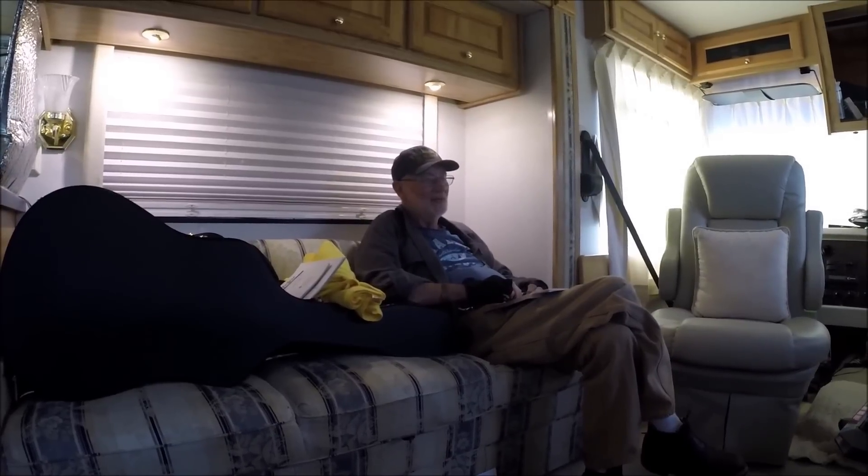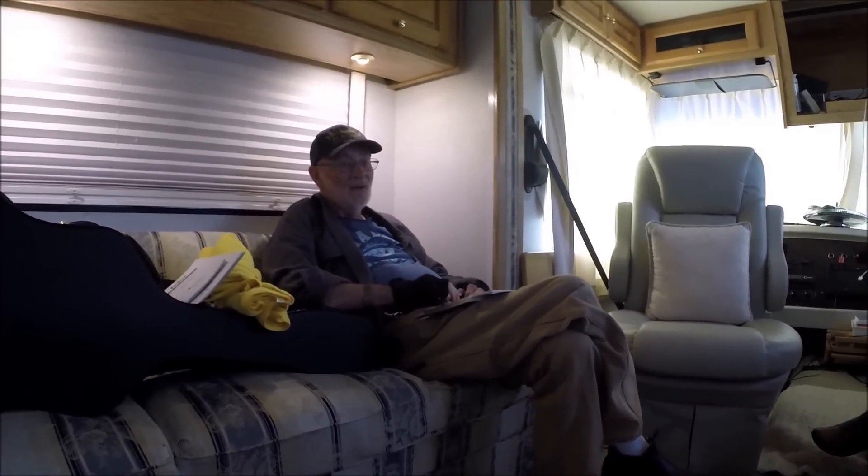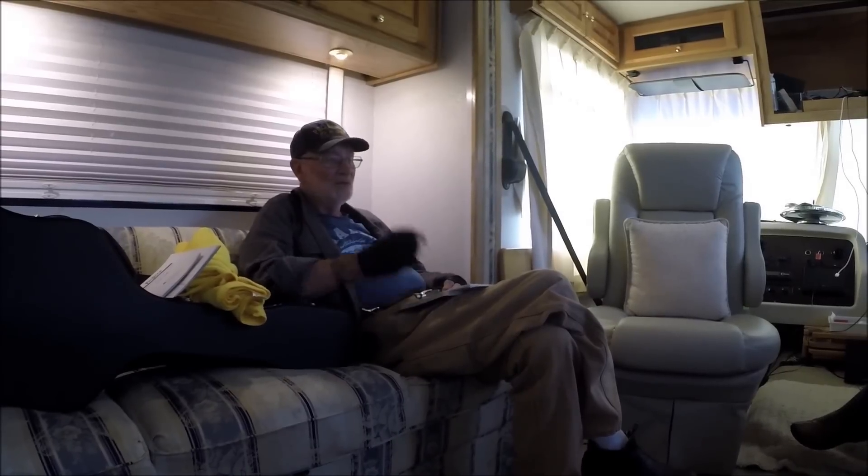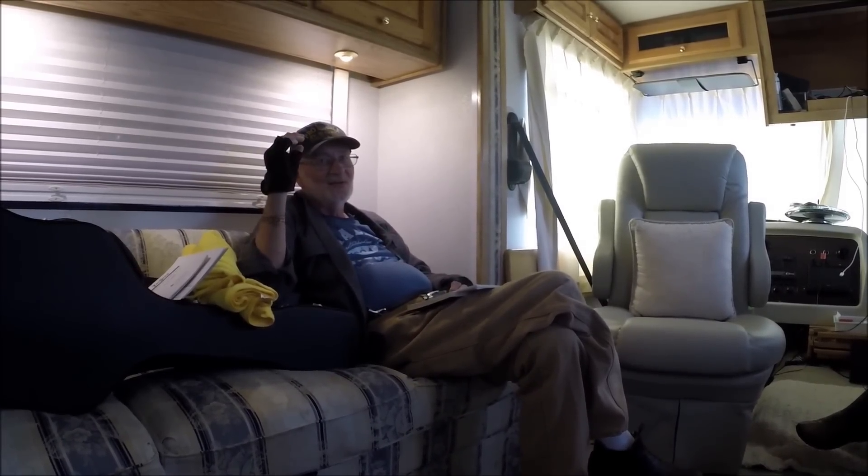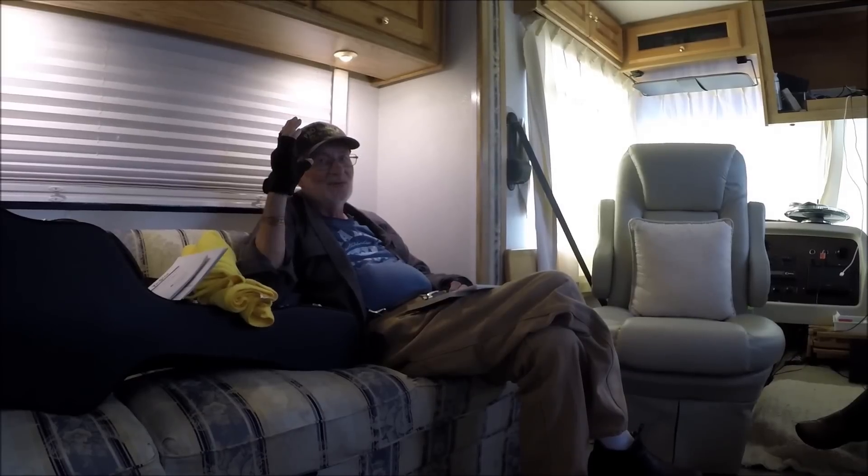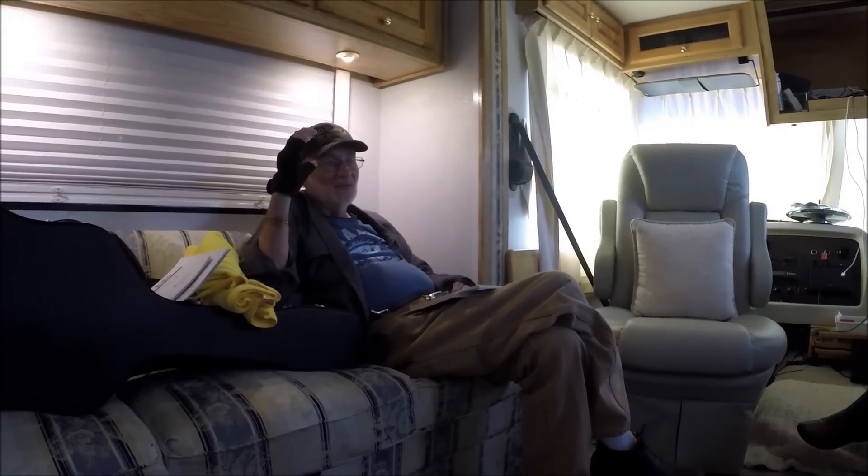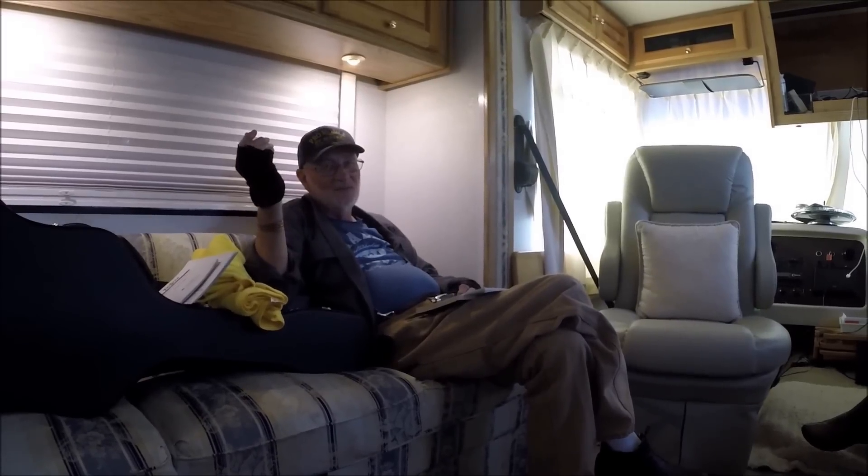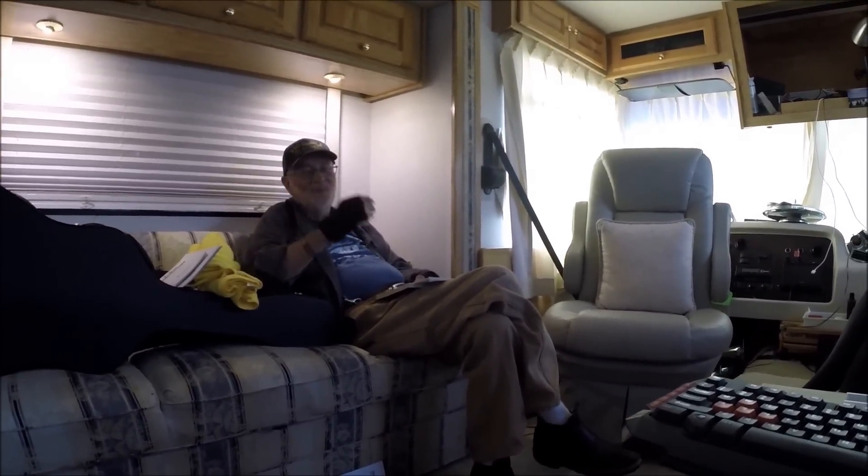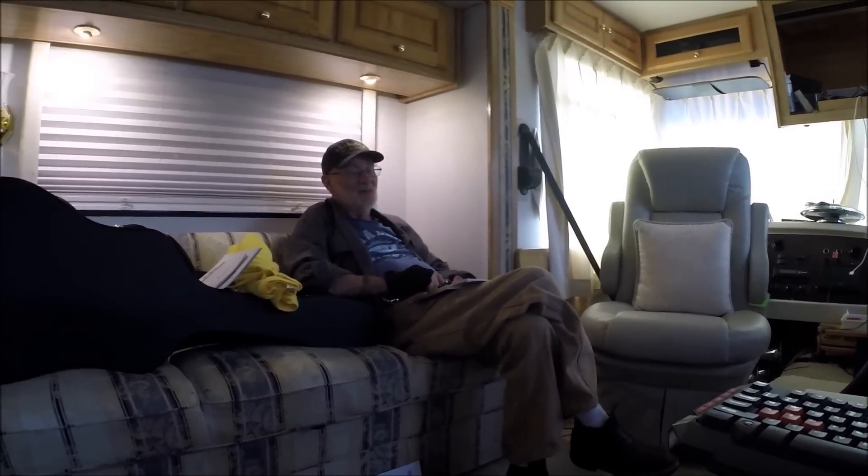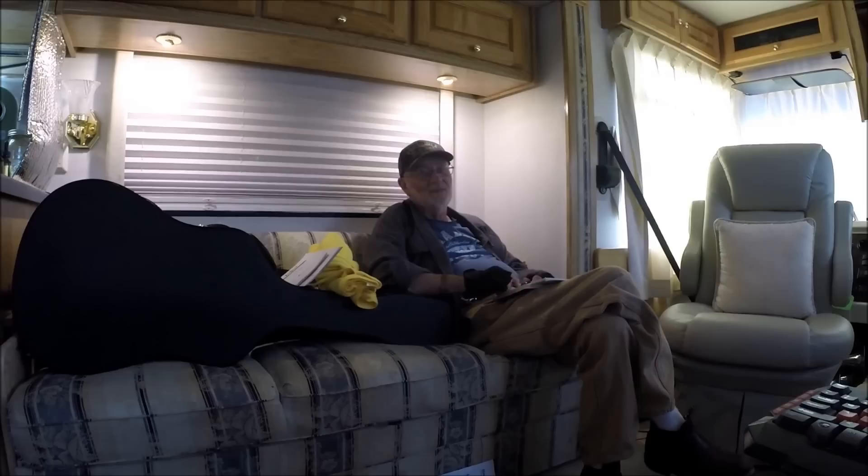We usually put at least a thermal breaker, something like a 50 amp thermal breaker in line. If you get a short, the thermal breaker will kick right out and it stays open. And pretty soon it'll try to close again, and if it's still got overloaded it'll pop open. But the nice thing about them is you don't have to hand reset them and you don't have to replace them unless they burn out.